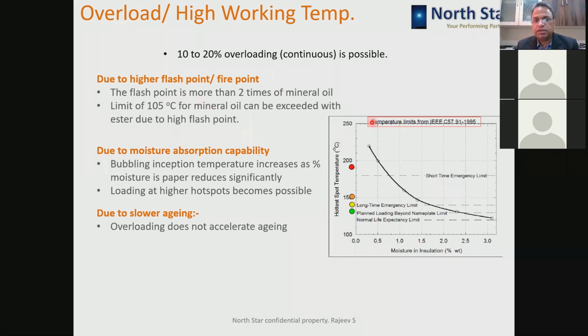Here it is shown in this graph the hottest spot temperature and moisture in insulation. Okay, so the more the moisture, the ability to overload the transformer is lower. Okay, if the moisture is 0.5, probably you can take the transformer up to 200 degree centigrade temperature. The property which decides the loading of the transformer is basically, other than fire point, also moisture absorption in the transformer. If the moisture is high, the bubbling inception happens at a lower temperature.